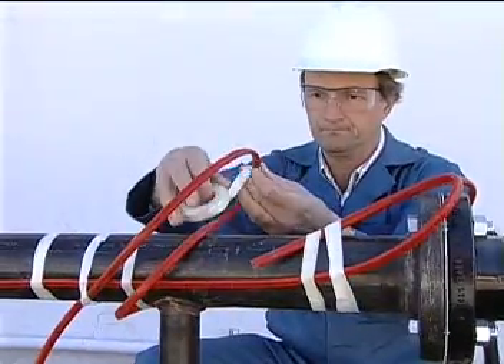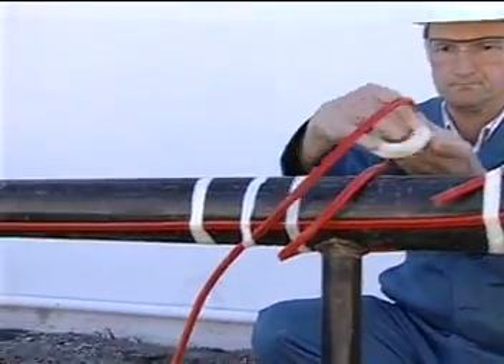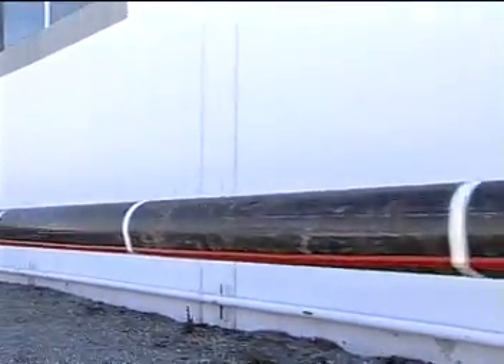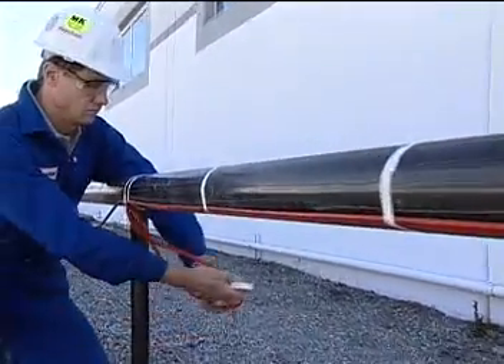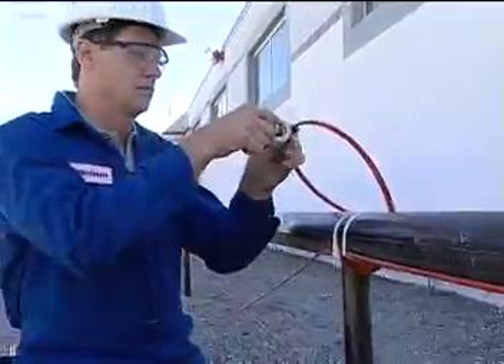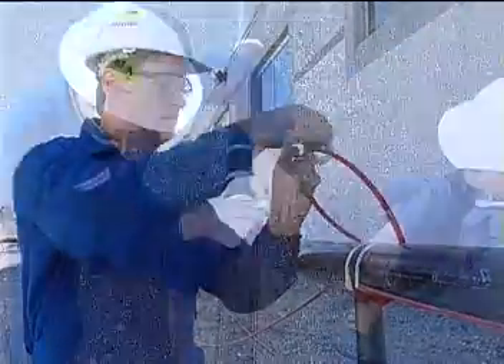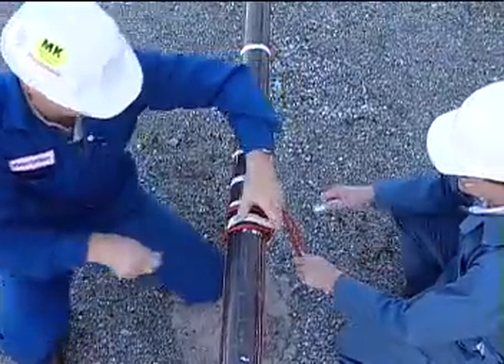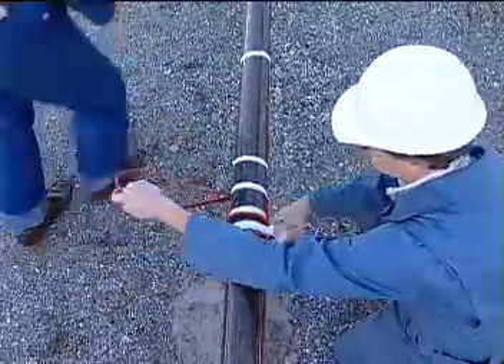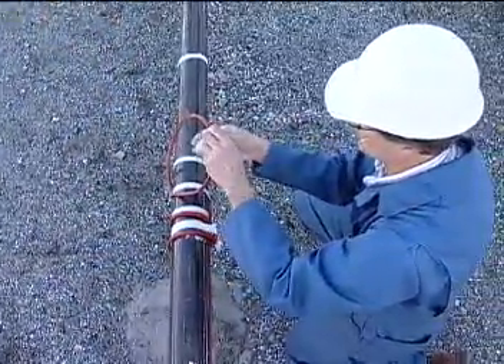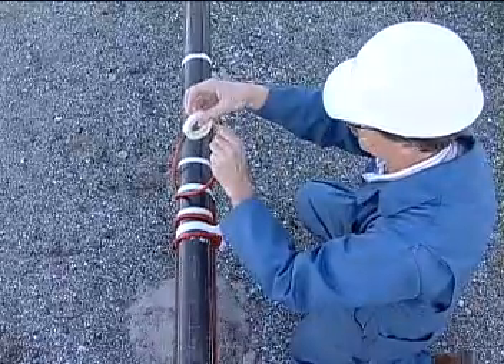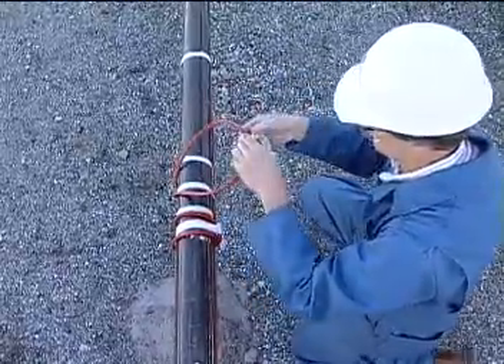You will still need to allow extra cable from each reel for the heat sinks. However, alternate which reel supplies the extra cable at each heatsink. This will assure that the overall length of each cable will be the same. If you're installing a second cable as a backup system, the second cable will need to be installed exactly the same way as the first. This means that there will need to be extra cable at each heatsink, as well as service loops on each end.